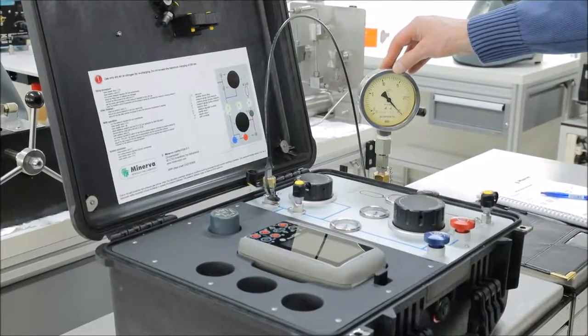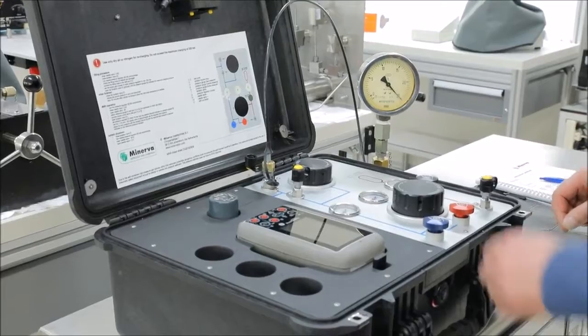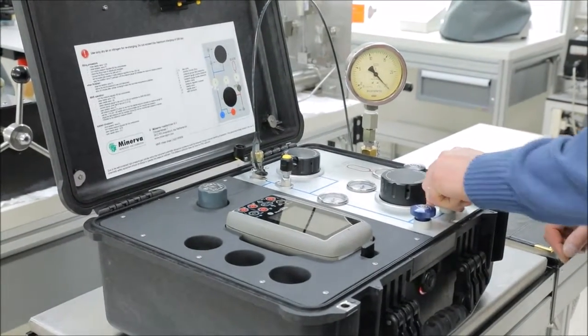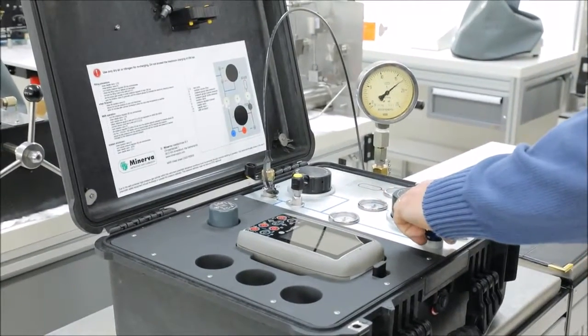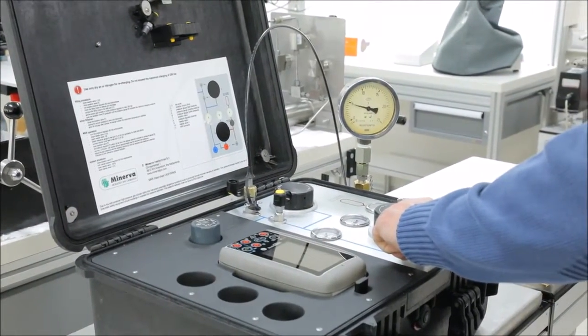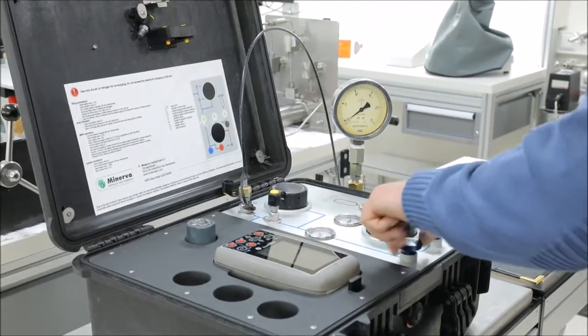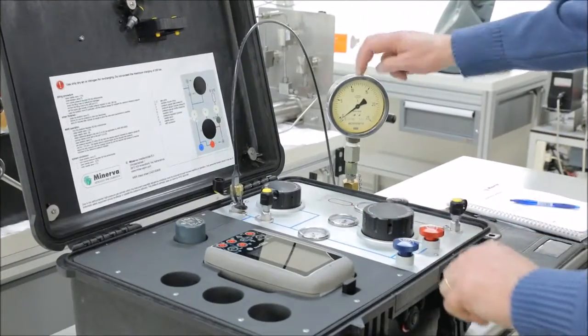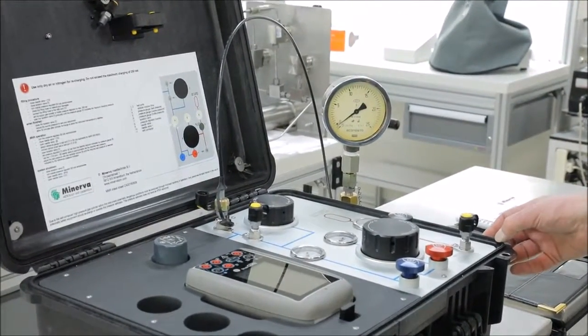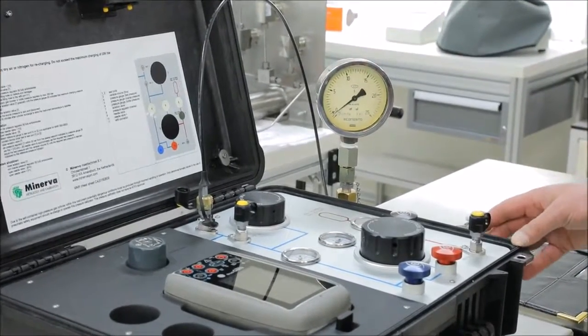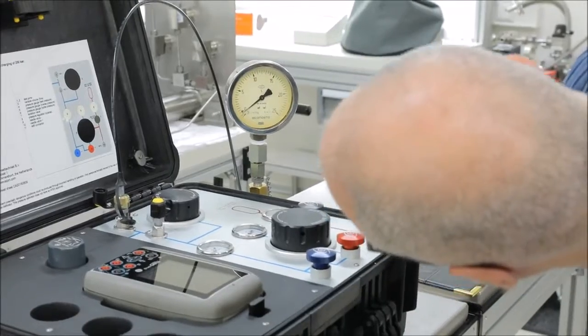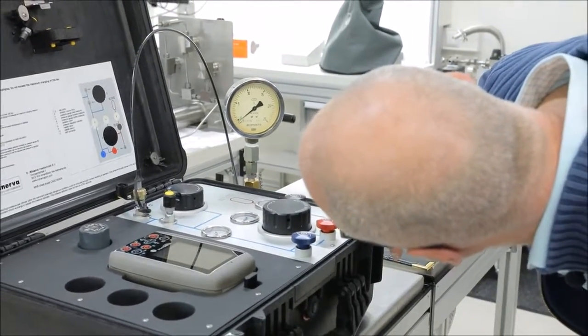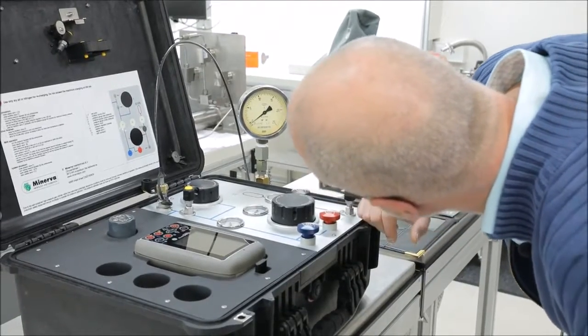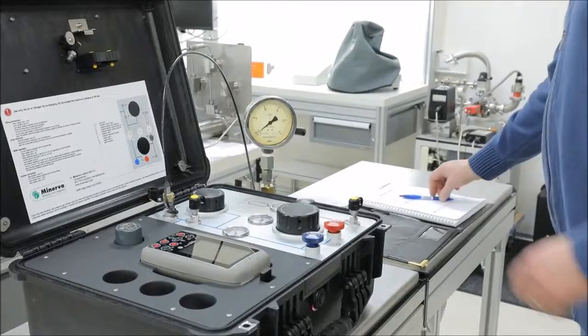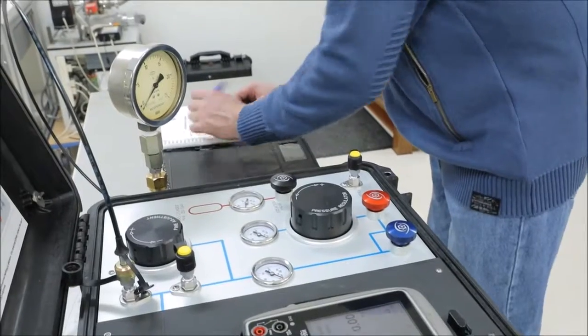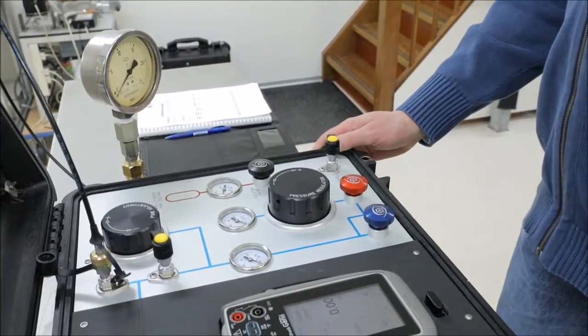Typically, when performing a calibration of an analog gauge, we will start at 0. So I will make sure my up valve is closed, and I will vent the system in a controlled manner. I can tap my analog gauge. And this is my first calibration point. So I will check the reading of my device under test. It's slightly below 0, and I'll make it minus 0.5 bars. And I'm ready to go to the first pressure point.